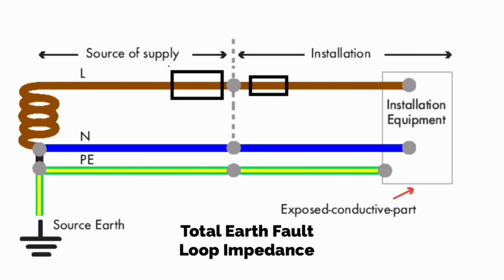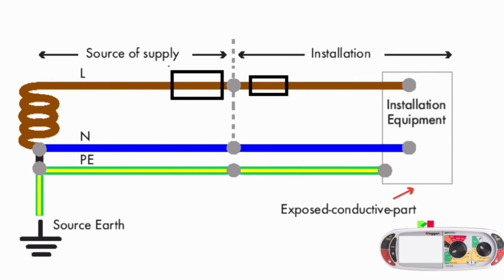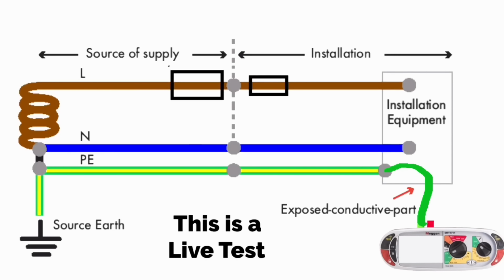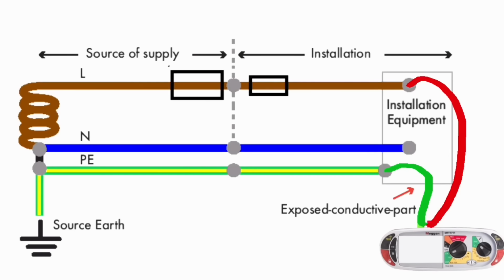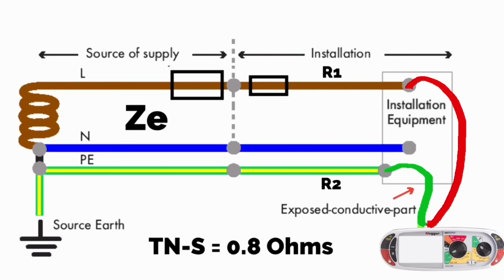Total earth fault loop impedance, ZS, is measured at the furthest point of a radial circuit and comprises the impedance offered by the line conductor, R1, the impedance offered by the circuit protective conductor, R2, and the impedance offered by the supply authority's cable. The maximum impedance of the supply authority's cable depends on the earthing arrangement. The drawing shown here is a TNS earthing arrangement. The supply authority's maximum impedance of that cable, ZE, is 0.8 of an ohm.